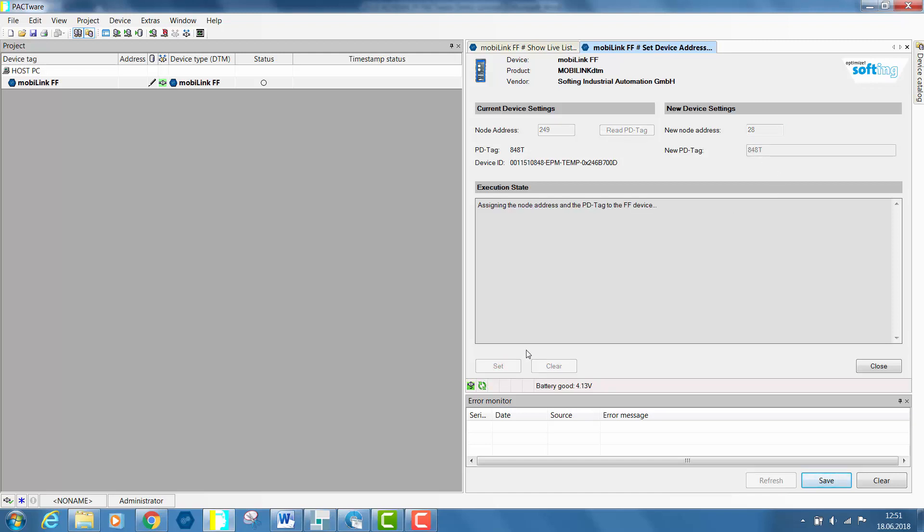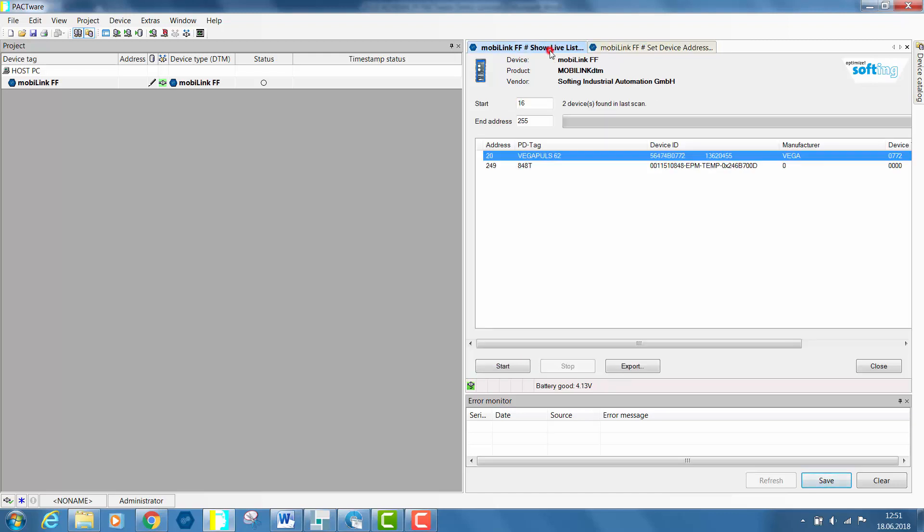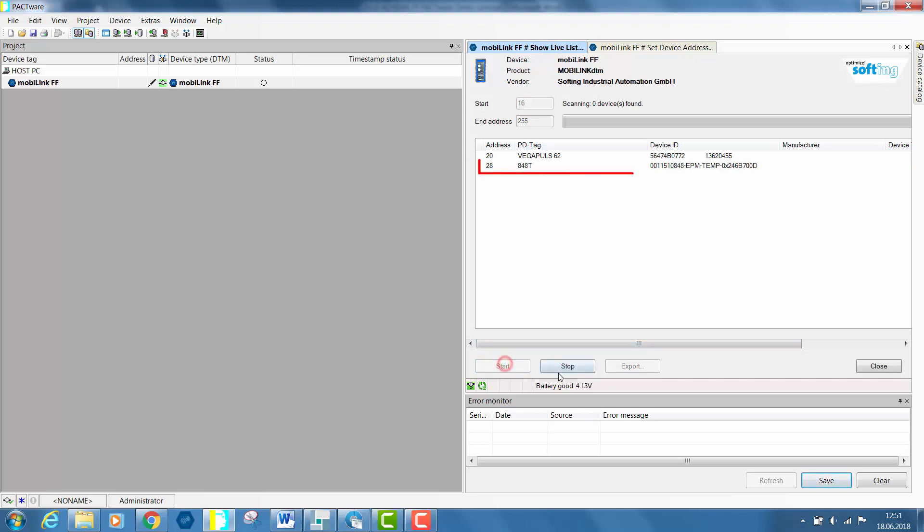The MobiLink is now communicating with the field device to change the node address value. You can verify that your value has been properly configured by refreshing the Show Live List. You will notice that the Rosemount sensor has got the address value 28.